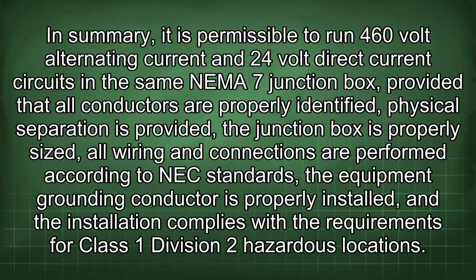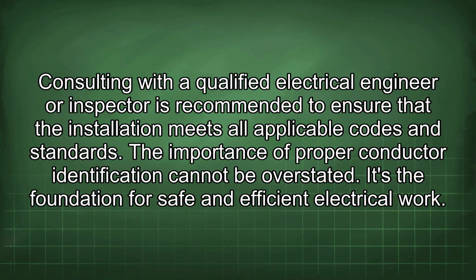the same NEMA 7 junction box, provided that all conductors are properly identified, physical separation is provided, the junction box is properly sized, all wiring and connections are performed according to NEC standards, the equipment grounding conductor is properly installed, and the installation complies with the requirements for Class 1 Division 2 hazardous locations. Consulting with a qualified electrical engineer or inspector is recommended to ensure that the installation meets all applicable codes and standards. The importance of proper conductor identification cannot be overstated.